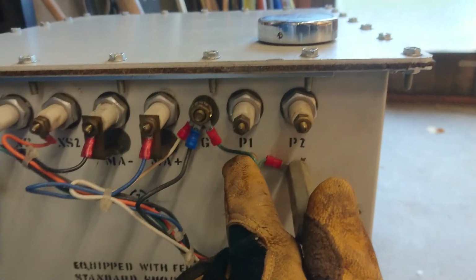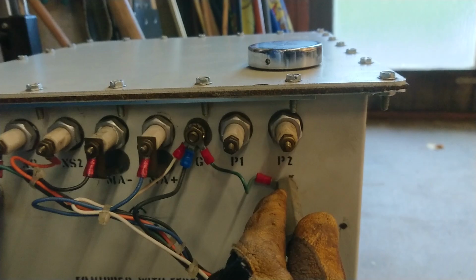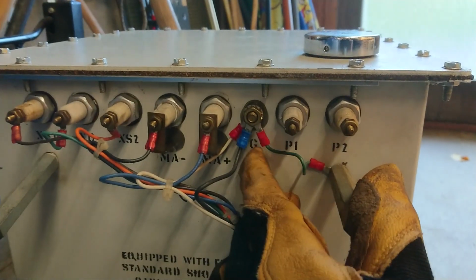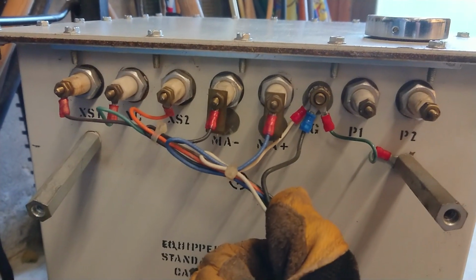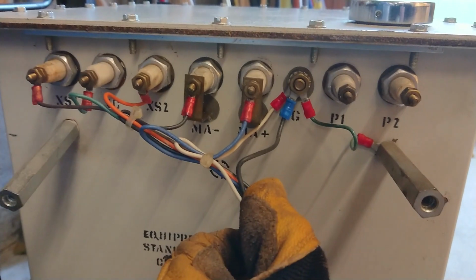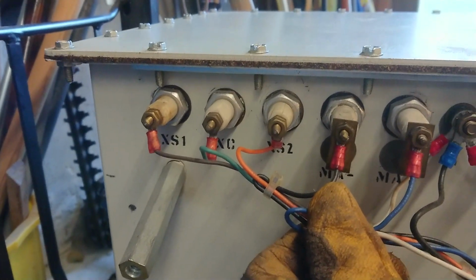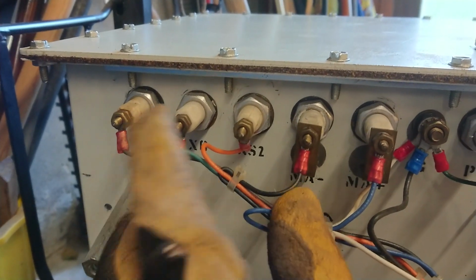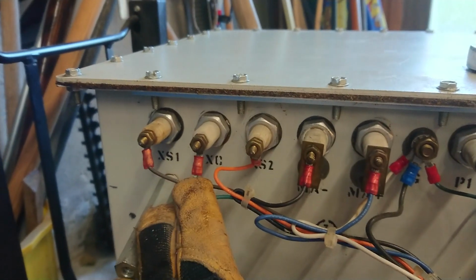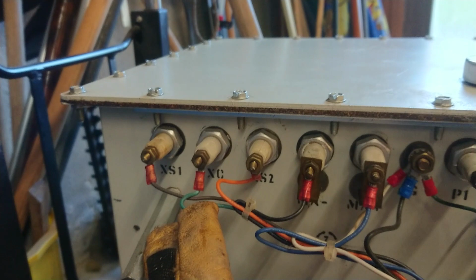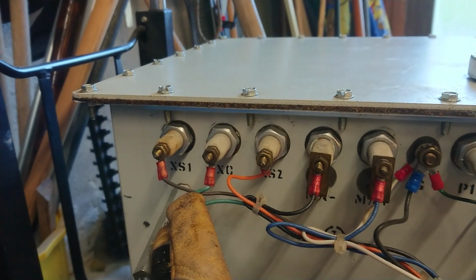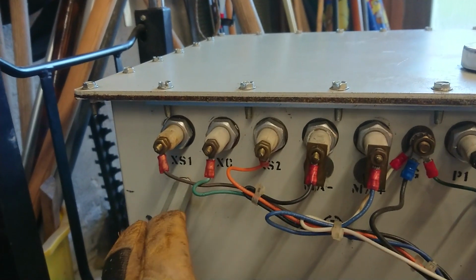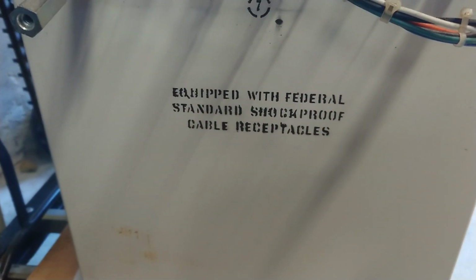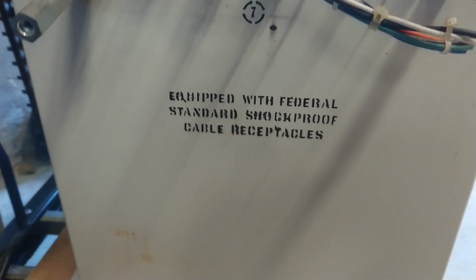At first we have P1 and P2, which are the primary inputs. Then there is G for ground. Then we have milliamp minus and plus for the milliamp measurements. Then there is XS1, XS2 and X common. These are for the 2 strings to measure the peak voltage on each string, as this is midpoint grounded. It also says down here, equipped with federal standard shockproof cable receptacles.